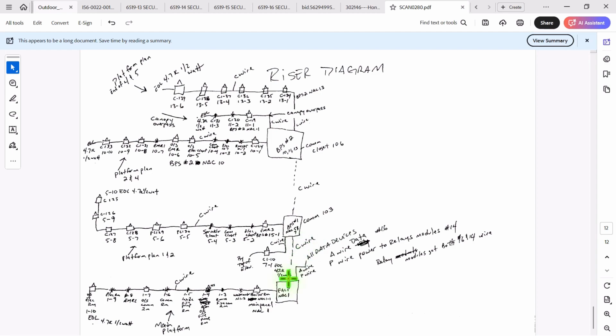We show a line break connecting to the first booster panel. Booster panel 1 has circuits 5 and 7, like I showed before, with 5 connected to all of these devices, and 7 just that one device above elevator number 3. Then this booster panel connects to the next one, also supervised with a 4.7K resistor. Coming off circuit 10 will be these devices.